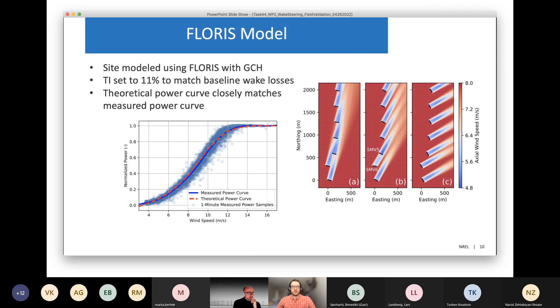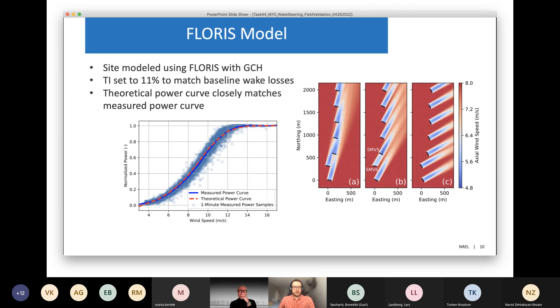For comparing model predictions with field results, we used a FLORIS model — specifically the Gauss Curl Hybrid model, FLORIS version 2.3 or 2.4. We tuned FLORIS to match the average wake losses observed by tuning the turbulence intensity parameter — a TI of 11% matched the baseline wake losses well, closely agreeing with the average turbulence intensity measured by the ground-based lidar. We also verified that the theoretical power curve used as input to FLORIS matched the measured power curve very closely.